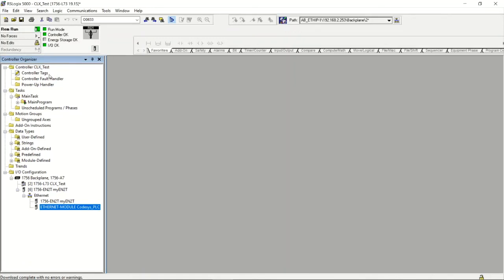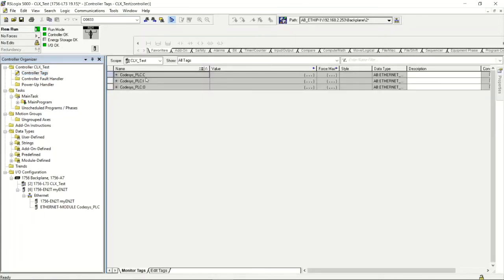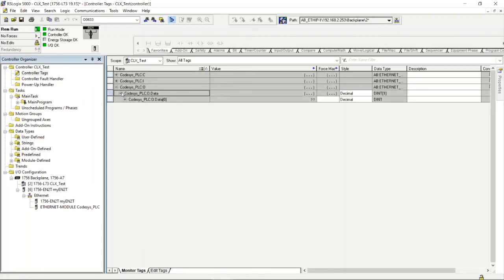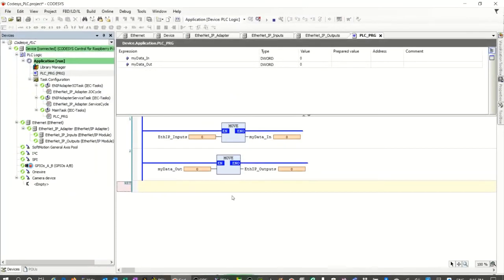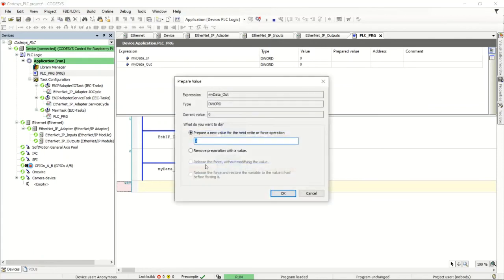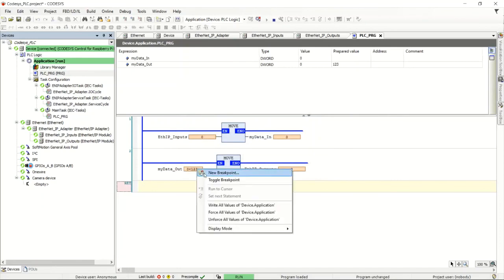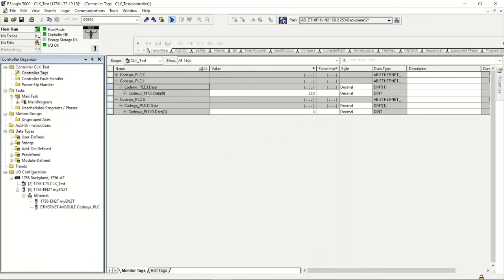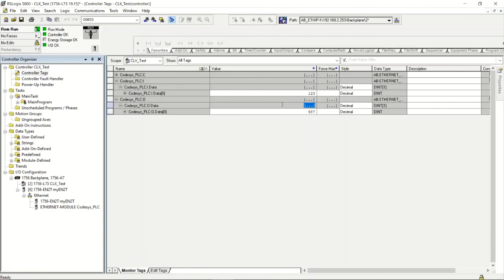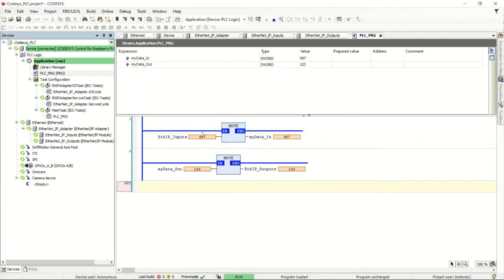Let's go into the tag database — this is where Rockwell stores its tags — and monitor the data going in and out. In CodeSys I set 'data_out' to 123; that value appears immediately in the ControlLogix input tag area as 123. Then in ControlLogix I set the output tag to 987, and switching back to CodeSys you can see 987 arriving as an input.